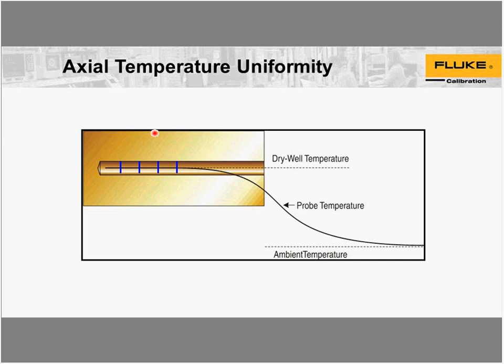Secondly, CG13 defines the number of steps. The number of steps may depend upon your application. The intent is that many thermometers will have a sensor length of 20 to 40 mm, sometimes a little longer, and what you want to be sure of is that you cover that sensor length.